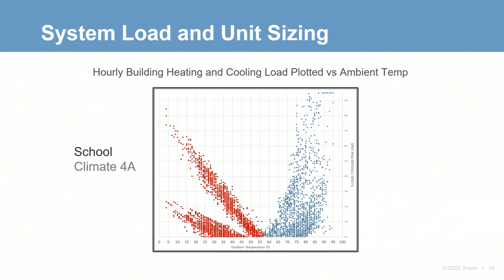Each point on the plot represents an hourly load point as a function of outdoor air temperature over a typical calendar year. The cloud of points in blue and to the right represents cooling load, and in red to the left are heating loads. A couple of interesting trends to call out. The higher grouping to the left is occupied heating loads, and the lower grouping to the left is unoccupied heating loads. The difference is driven by the increased requirement for ventilation air during those occupied times.